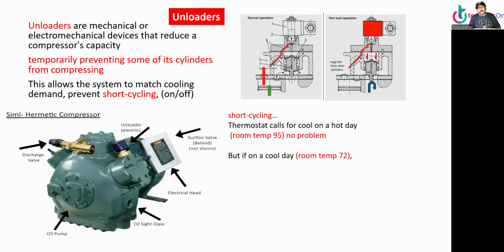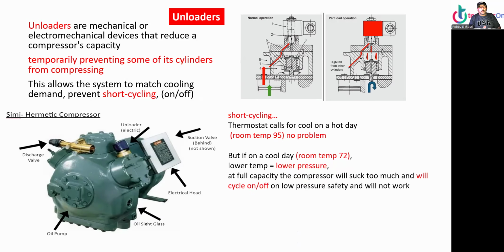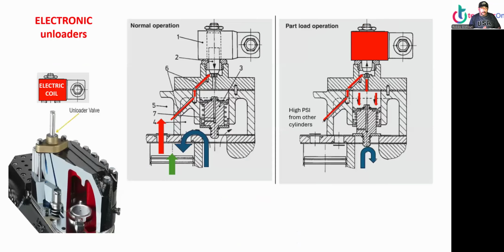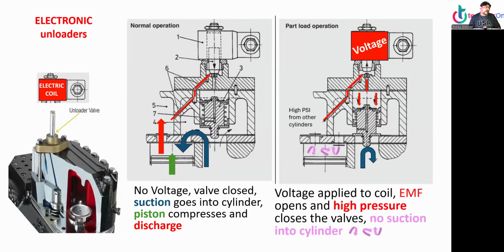But on a cold day, room temperature 72, low temperature equals low pressure. At full capacity, the compressor will suck too much and cycle on and off on the low pressure safety and will not work properly, on off too much. So we need unloaders. Unloaders control the capacity, the horsepower, of a compressor. Now, electronic unloader energized by voltage: no voltage on the left, valve closed, suction goes into the cylinder, piston compresses and discharges normal. Voltage applied to the coil opens it, and high pressure closes the valve, no suction. You can see now one of the valves is not working, one of the valves is not moving.